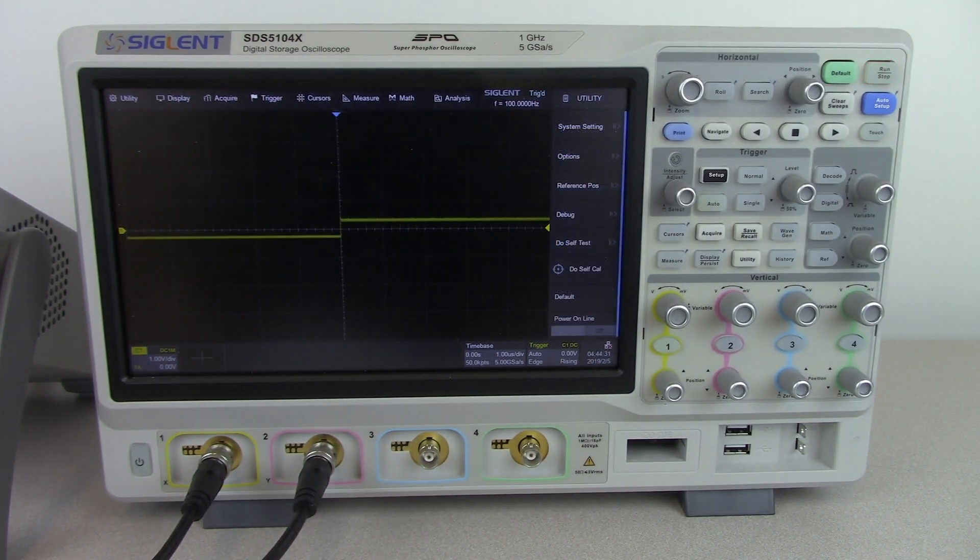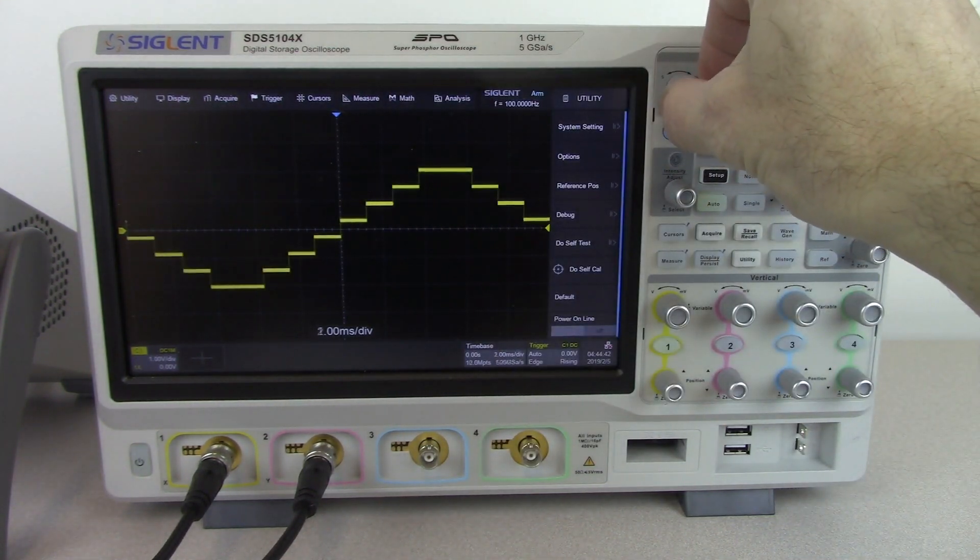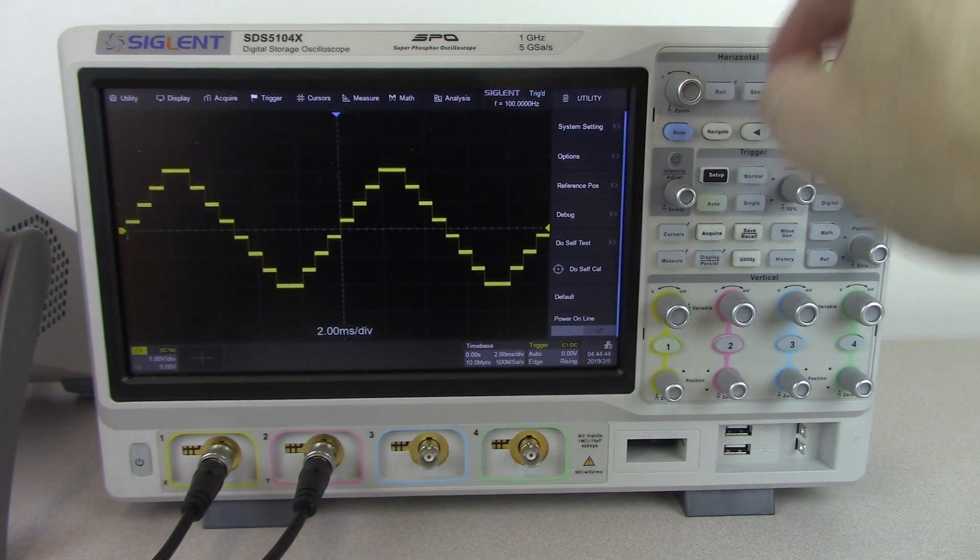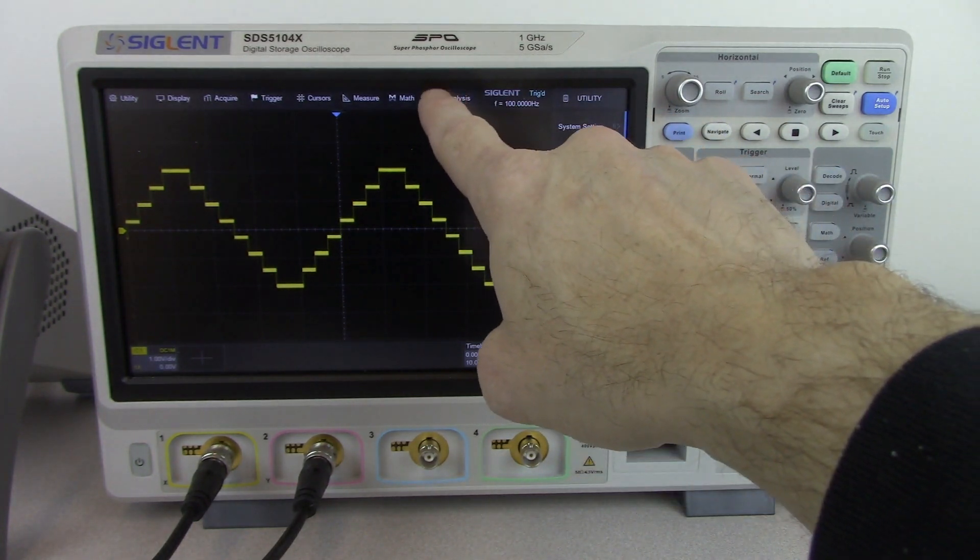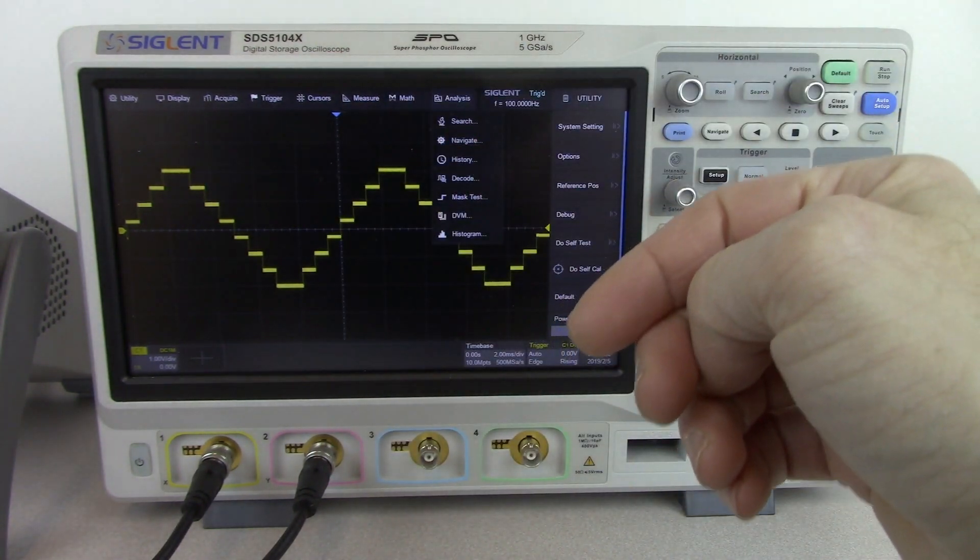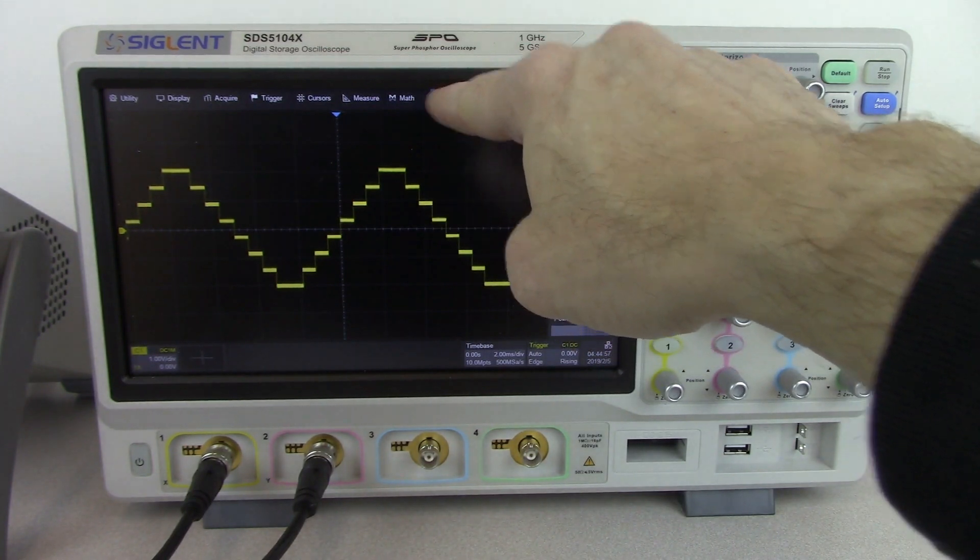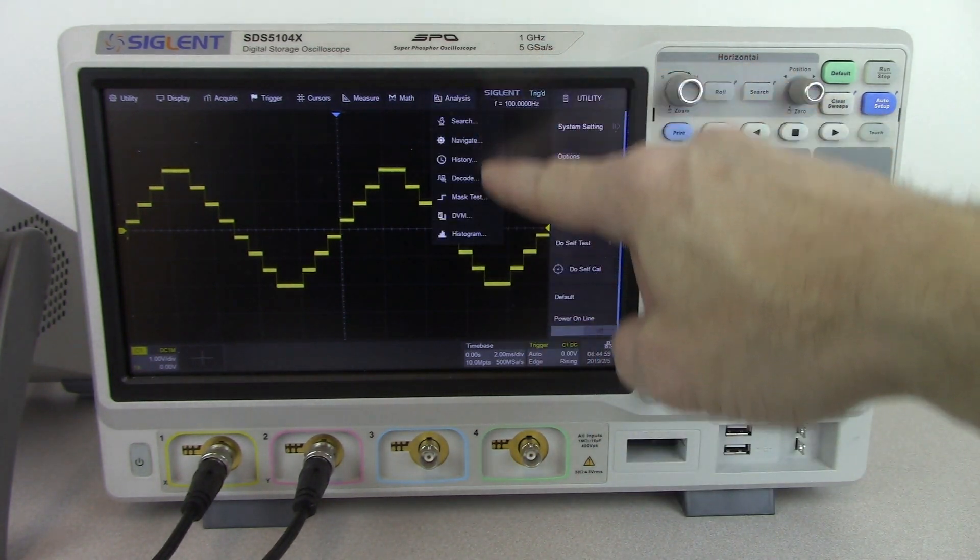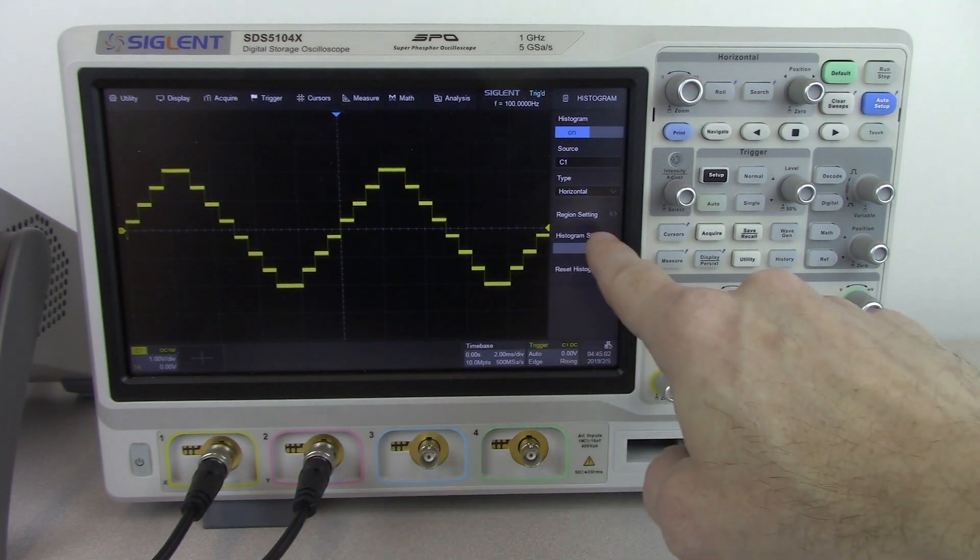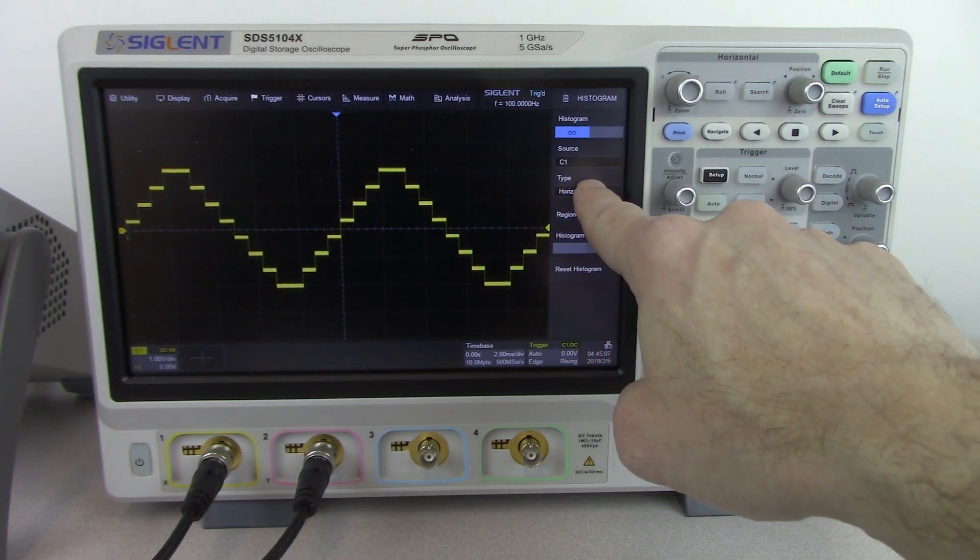Now I would like to introduce the waveform histogram function of the SDS5000. In this case, I've got a stair step output here using the signal generator. To enable waveform histogram, which is going to give you an analysis of the bins that have been hit or the pixels that have been occupied by a particular waveform or series of waveforms, we want to press analysis to open up that menu. We're going to go to histogram. I'm going to set this to vertical because it's more interesting.